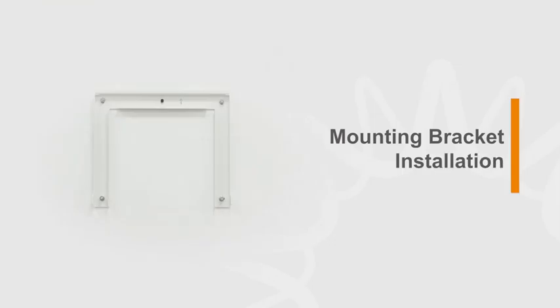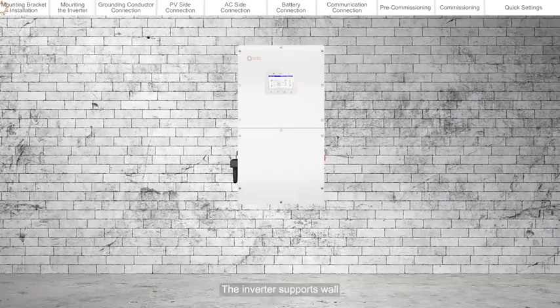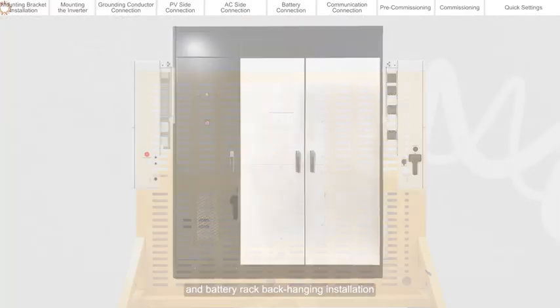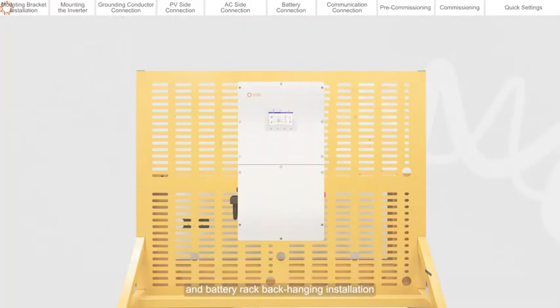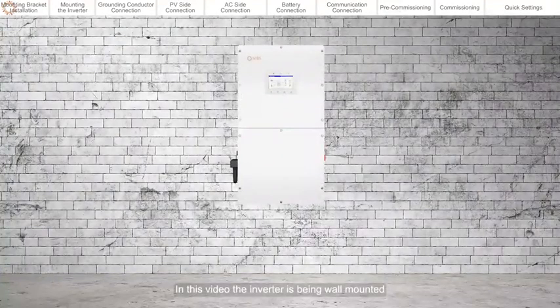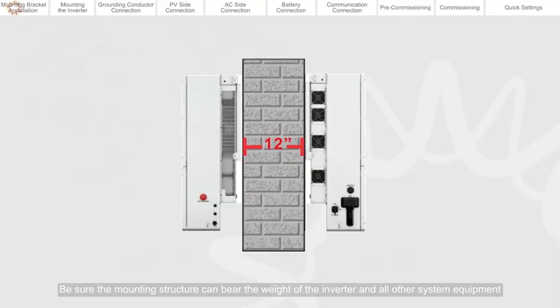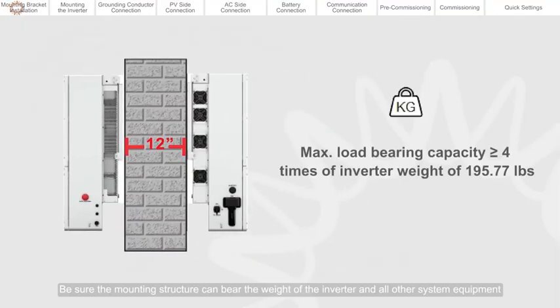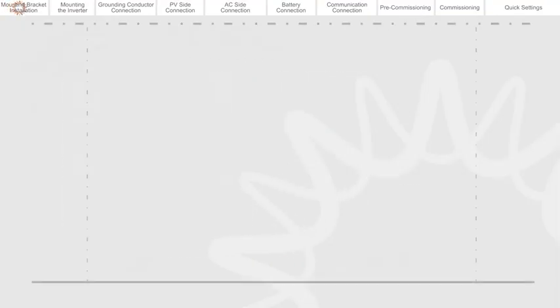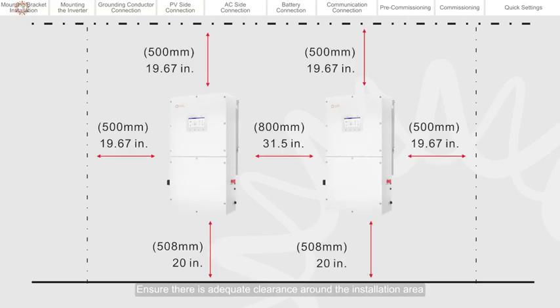Mounting bracket installation. The inverter supports wall, battery cabinet, and battery rack back hanging installation. In this video, the inverter is being wall mounted. Be sure the mounting structure can bear the weight of the inverter and all other system equipment. Ensure there is adequate clearance around the installation area.